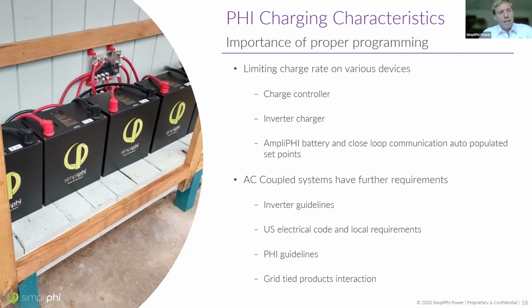The nice thing about the AmpliPhi battery, the battery with communications built in, is that it will tell the inverter how quickly it wants to be charged, how quickly it wants to be discharged, what its state of charge is, etc. These settings are auto-populated right into the inverter. So the AmpliPhi battery is more plug and play, a safer installation for solar installers, and it offers the feature that you can get notifications if there's a problem with your system, instead of waiting for the customer to call you back saying their batteries aren't working. This battery can be remotely monitored, as can our new batteries with our new inverter, the ones I presented to you earlier.